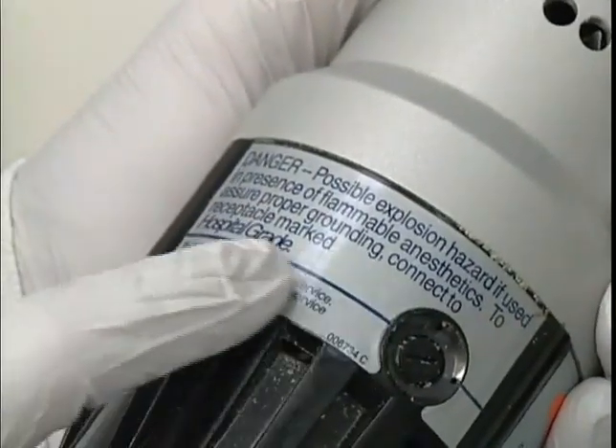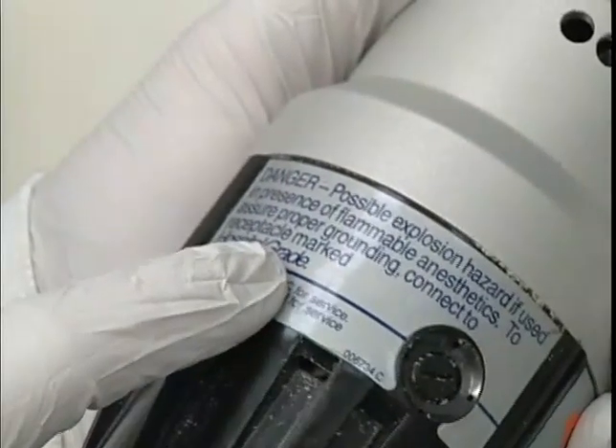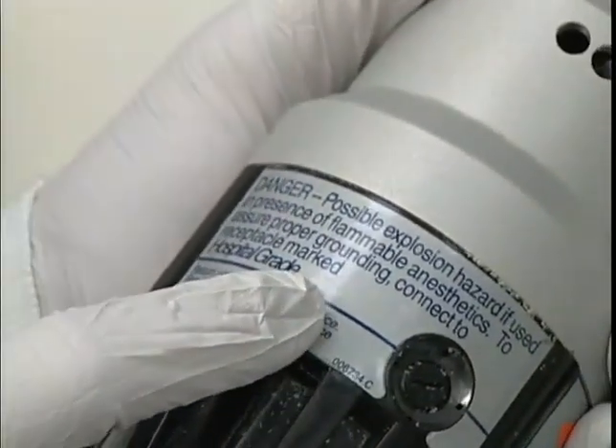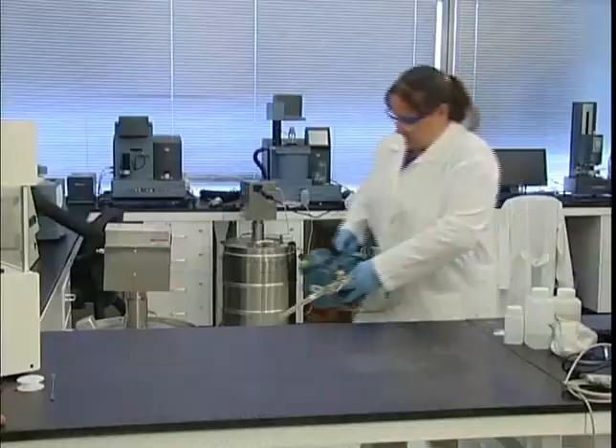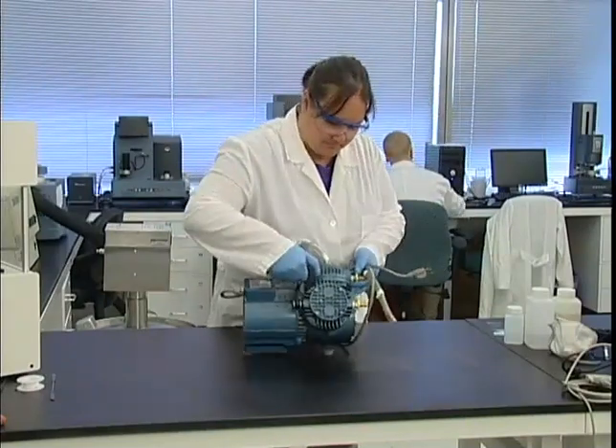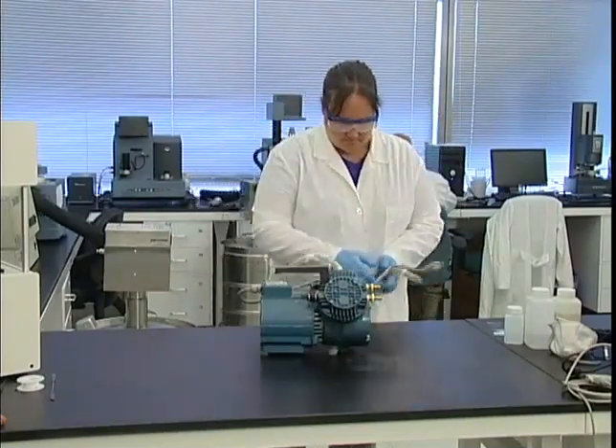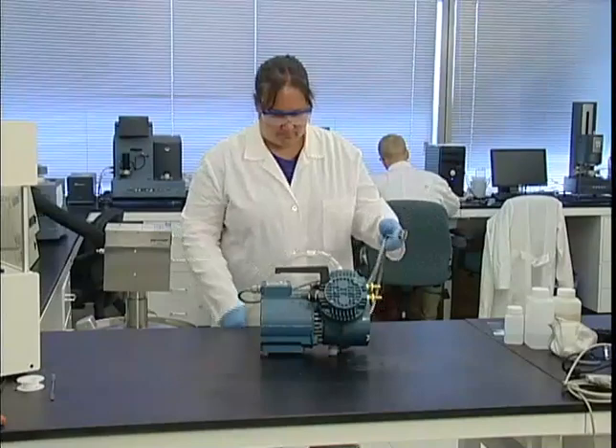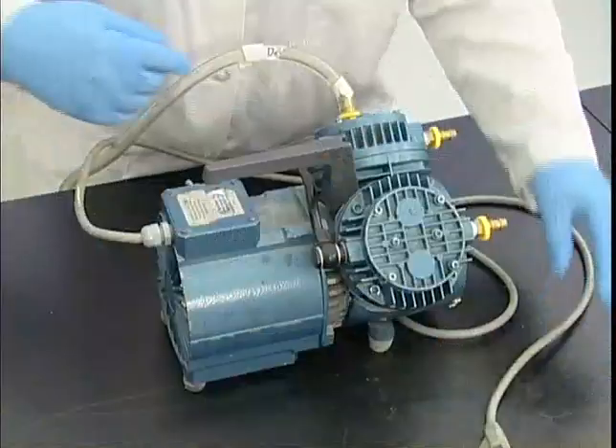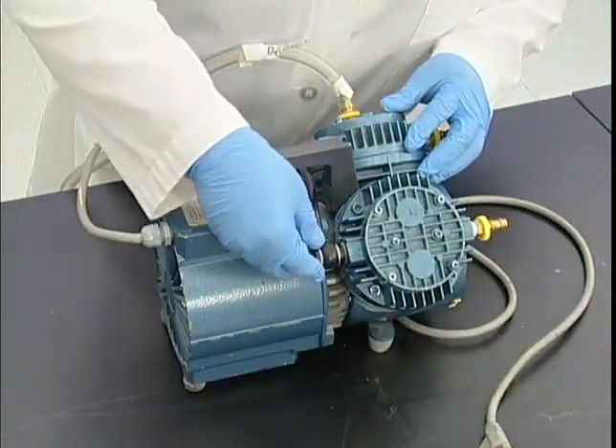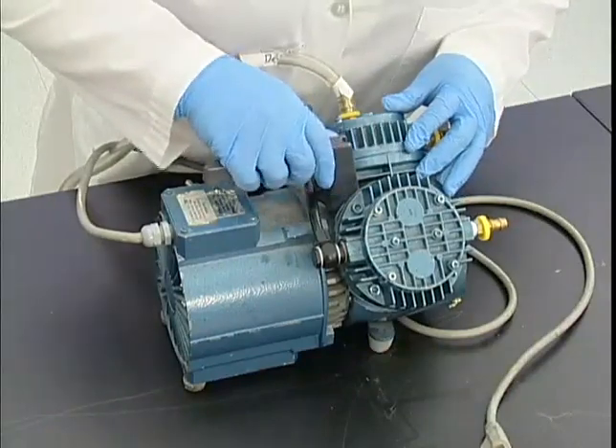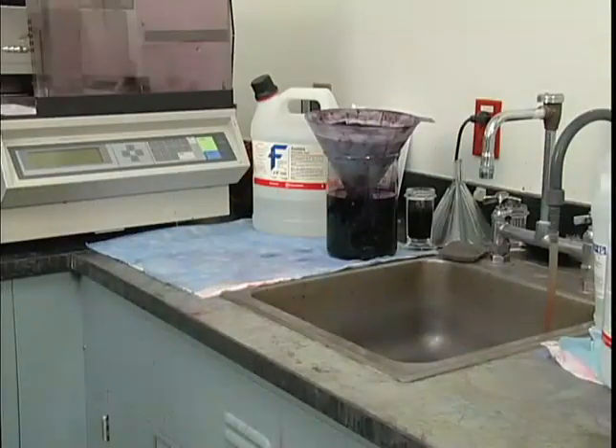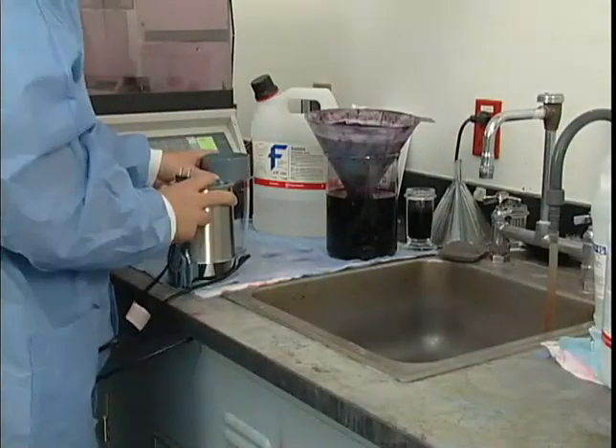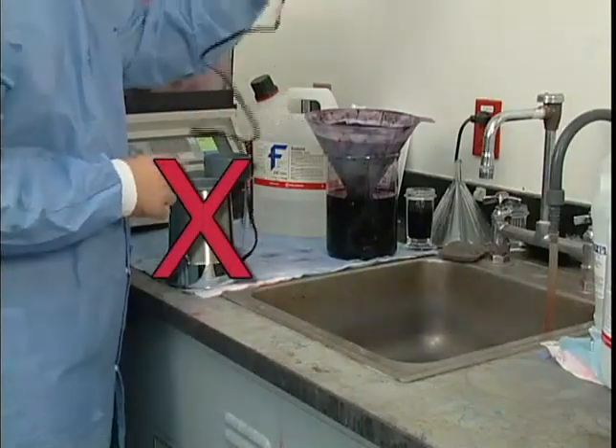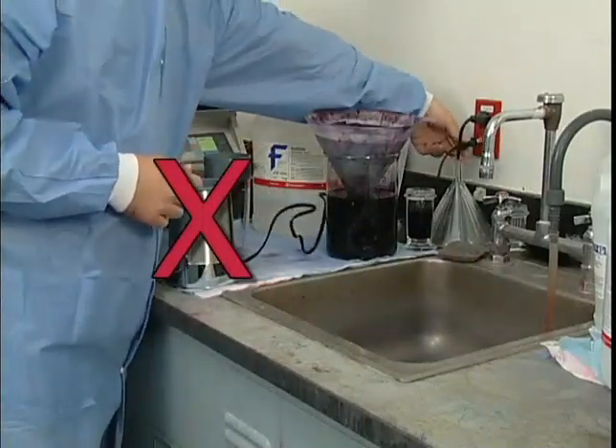In areas where flammable materials exist, it's especially important that you choose the equipment you work with carefully. Motor-driven electrical equipment should be equipped with non-sparking motors and switches that limit the possibility of an accidental fire. This includes items such as vacuum pumps, mechanical shakers, and stirring devices. Never bring home appliances into a lab where flammables are present. Most of them have switches that can spark.